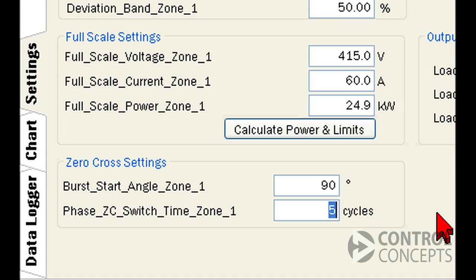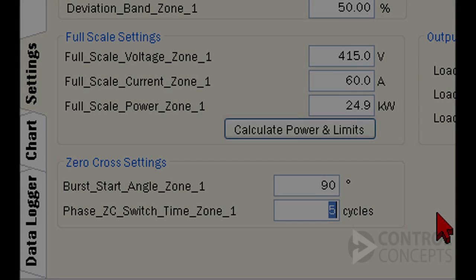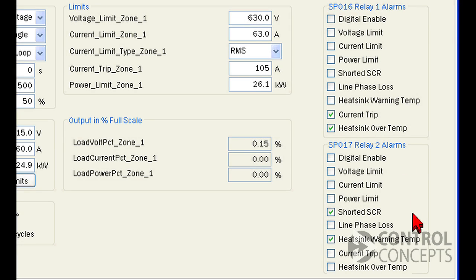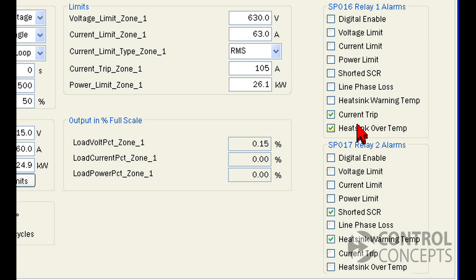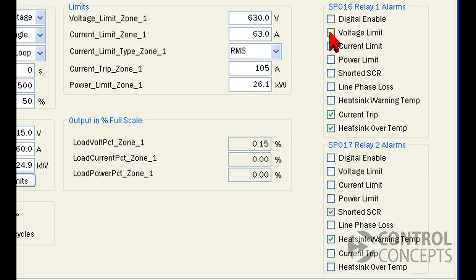Finally, let's look at our relay alarms. We check the box next to an alarm to direct it to a relay. By default, relay one is set to current trip and over temp, and relay two is set to shorted SCR and warning temp. You could check as many alarms as you want. Just note that if more than one are checked per relay, you won't be able to determine which alarm caused the fault, except by using the keypad display or accessing the information with digital communications.